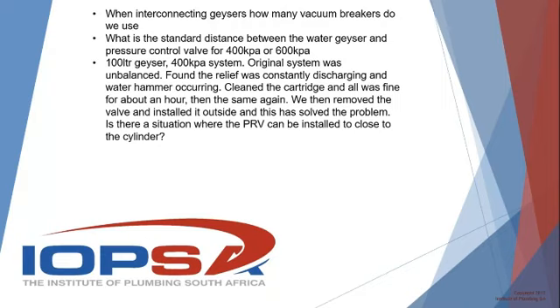Okay, the next question is quite long, but in essence, when the valve was installed close to the geyser, it was water hammering and constant discharge of the overflow, and then he moved the valve to the outside of the building, and that stopped for some other strange reason. The question is, can there be a case where the PRV is installed too close to the cylinder? And I can tell you that's a no.